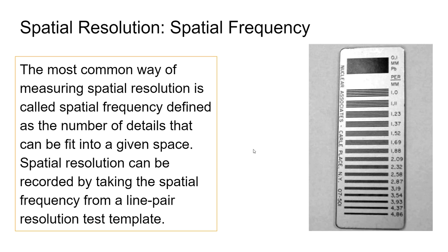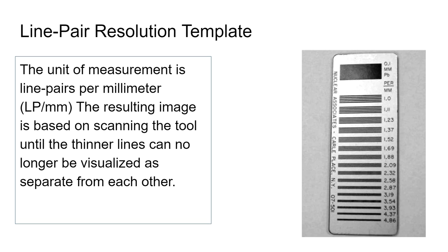And what we're measuring, we'll say that the spatial resolution is better or worse, but we're really looking at what's known as spatial frequency. So we're really looking at the number of details that you can see in a particular space. And that's going to ultimately be represented by pixels, a line of pixels. So as we've said, we're going to be looking at line pairs per millimeter.